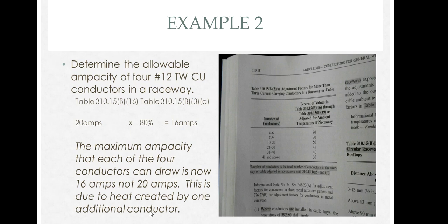The ampacity now for each of the conductors in this conduit can now draw only 16 amps and not 20 amps. This was due to the additional conductor in the raceway.